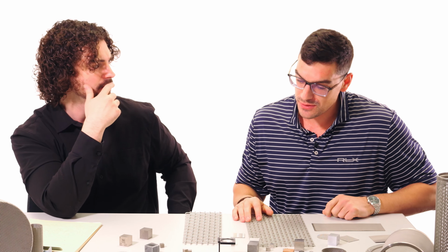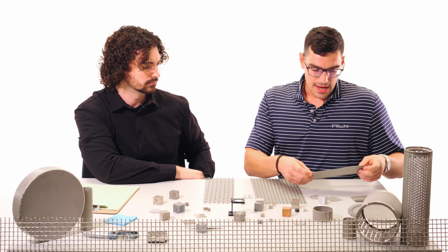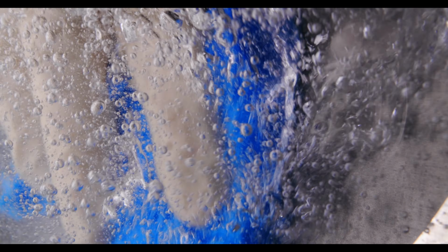So in a situation like that, how do you clean that? How do you get those particles out? There's a few ways you can clean, really. An initial way is called back flushing, which can be done by using a pulse of air. If there's particles that are lodged in your multi-layer surface and your flow is coming in this way, all your particles are going to either get stuck on the outside or on the inside. So you would initiate a back flush, which would hopefully dislodge the particles that are stuck on the outside or on the inside.